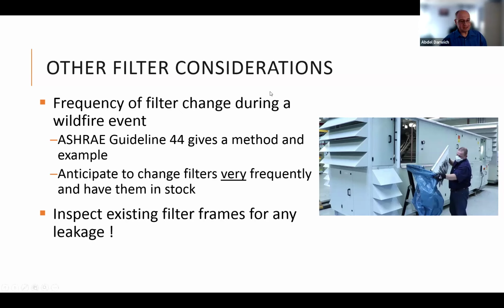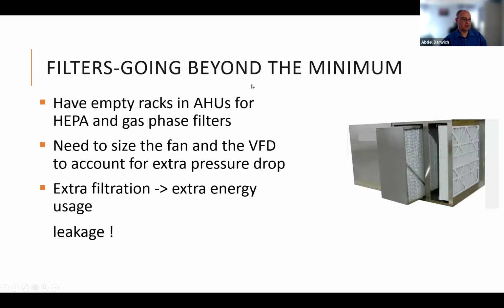More importantly, instead of thinking, well, I want a better filter, before you do that, inspect your filter frame. I mean, people should inspect the frame for any leakage, because leakage around the filter could really be a problem. You could install a MERV 13 filter, a very high efficiency filter, but because you have leakage around the filter, that filter is downgraded to nothing.